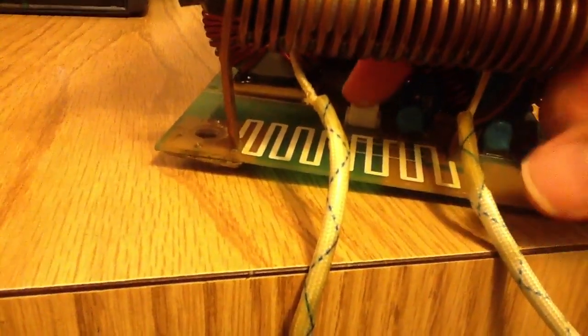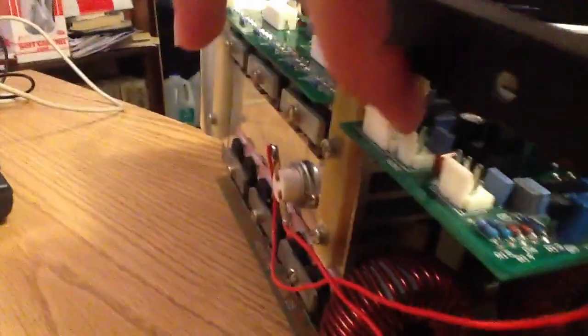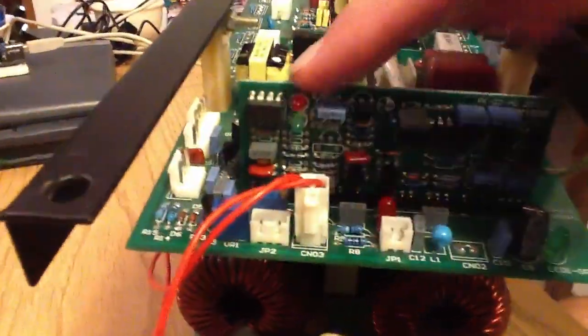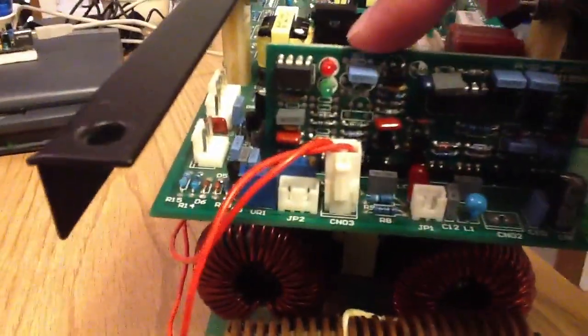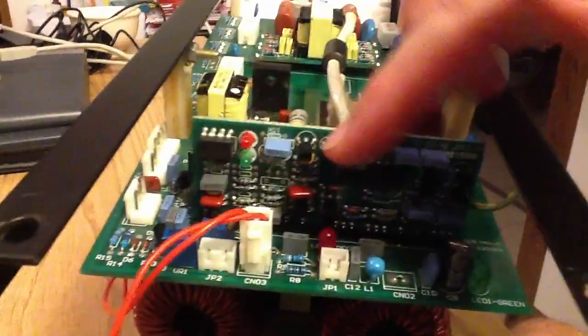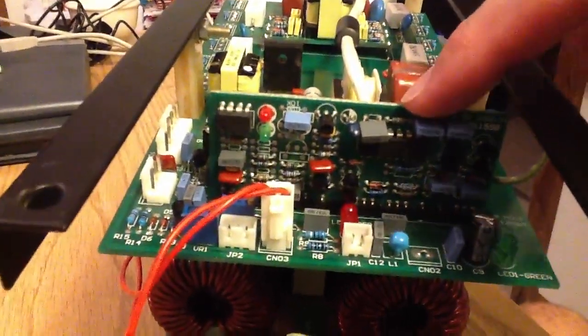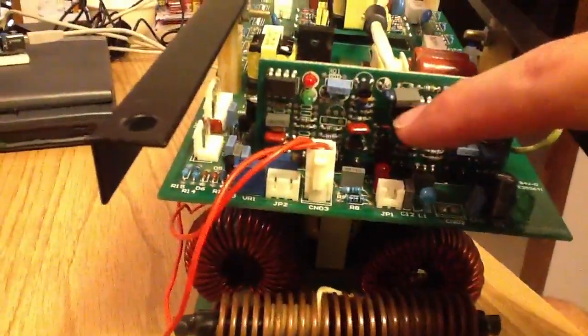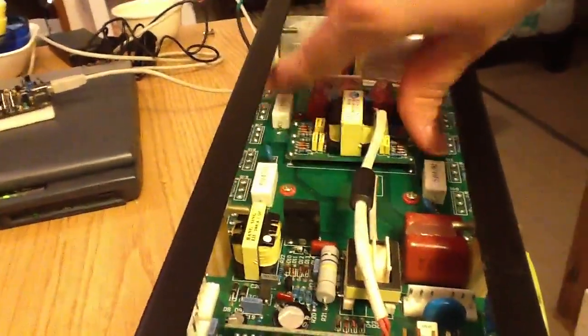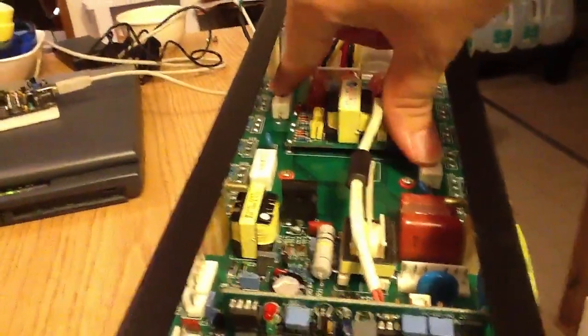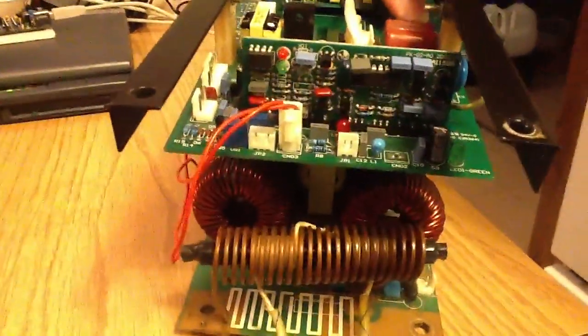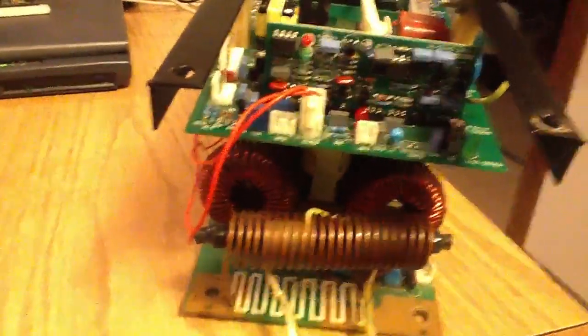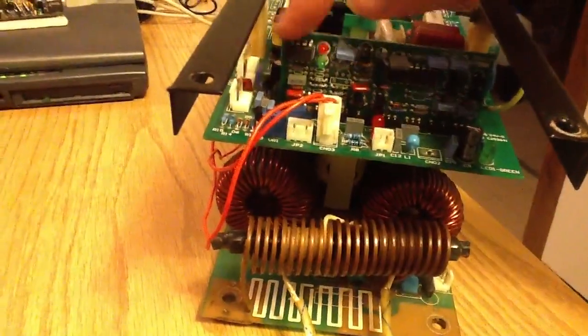It goes into this connector here and back up to this connector here on our control board, our main board, to feed the current signal back into the control circuit, so it can adjust the pulse width, in other words how long these stay on, in order to limit the current. Otherwise everything would just blow up, and you don't want that, of course.